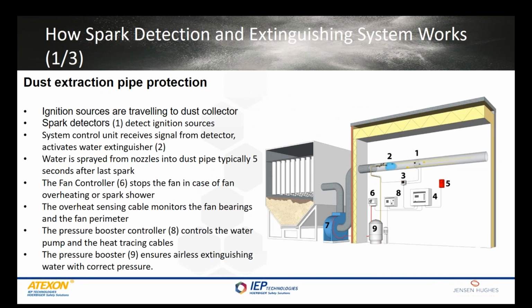Here we have a description of how the entire spark detection and extinguishing system works in a dust extraction system. You can see those yellow ignition sources or sparks traveling to dust collector. Oppositely installed spark detectors, number 1, react to sparks and send signal to system control unit, which then activates water extinguishing, number 2. Water is sprayed from nozzles into dust pipe, typically only for 5 seconds after last spark.